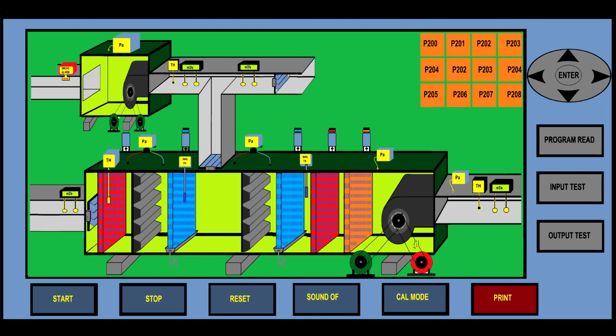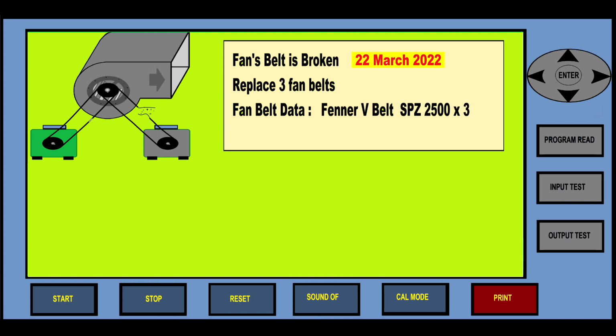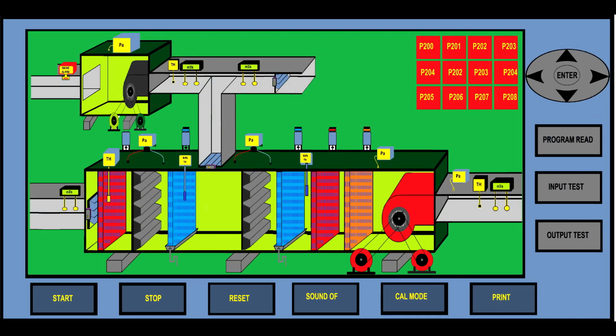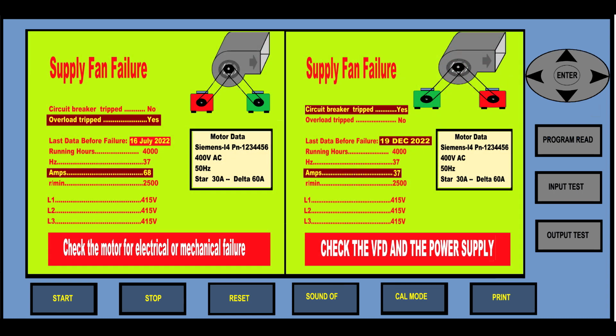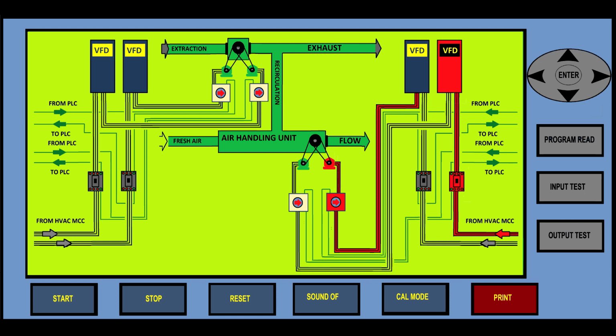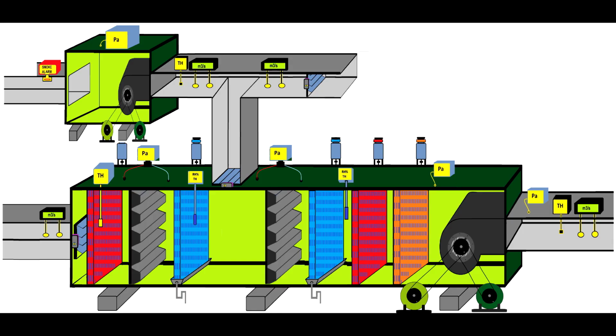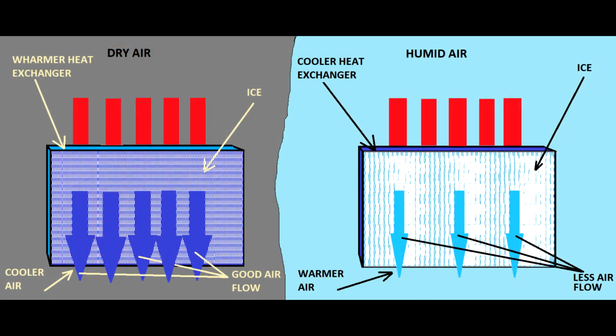If you have a broken belt, the new type of inverter has the capability to capture that, to send an instruction to the PLC, and the PLC will send data to the HMI, and the HMI will display a broken belt failure, and then also on the next page it will tell you what belt we're using and so on. This again is a disastrous failure in which a technician was reckless. He didn't repair the first motor, waited until the second one went down. The PLC will capture this, the SCADA will capture this, and it will show you what to do. And if you fix this, you'll have a good air handling unit.